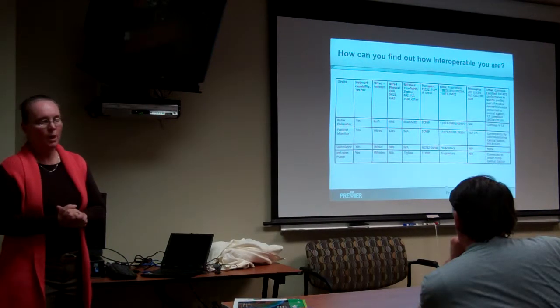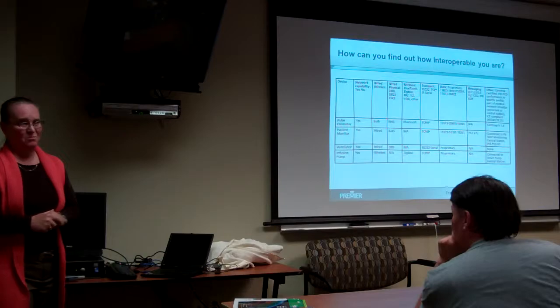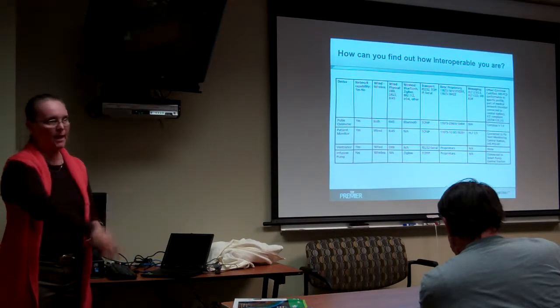Starting with that inventory, you have a goldmine of information to take to your IT team as they set priorities on which devices to build interfaces for. Just earlier this spring, I sat down with a woman in the Northeast responsible for the deployment of a new EMR. She had a list of devices to interface, and I quickly spotted two make-models where I knew the manufacturer no longer supported them. I said, you might want to rethink those — because why spend $10,000 to $15,000 per interface on devices that are no longer supported and will likely be replaced soon? Your IT team and CIO do not have this data unless they've dedicated a biomed individual. This is expertise you can bring to the table. If you don't have a relationship with your IT department, take them a gift — open the door.